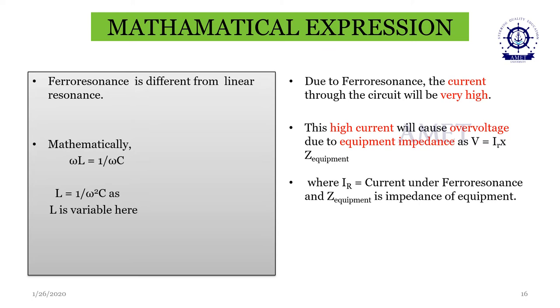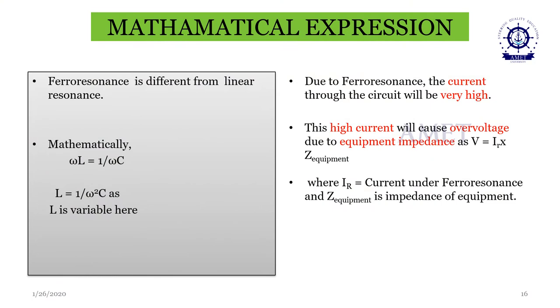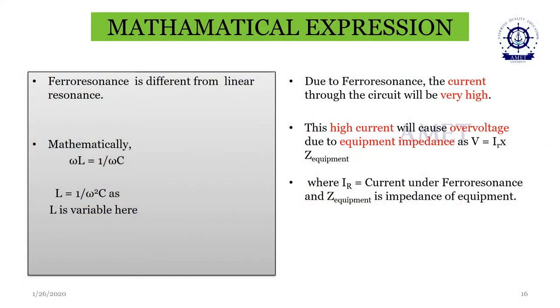Here ferroresonance is mathematically represented, because I said before that the transformer inductive reactance omega L is equal to the capacitive reactance, 1 by omega C. From that we try to find out the inductance. L is equal, just cross multiplying, to 1 by omega square C, where L is variable here. But in case of a normal resonance circuit, say a 50 hertz circuit network, L is fixed, it's a constant frequency, because it's only one particular frequency. But here L is varying. Why is it varying? Because the charges stored in the transformer are transferred into the capacitance. So L is variable in nature.